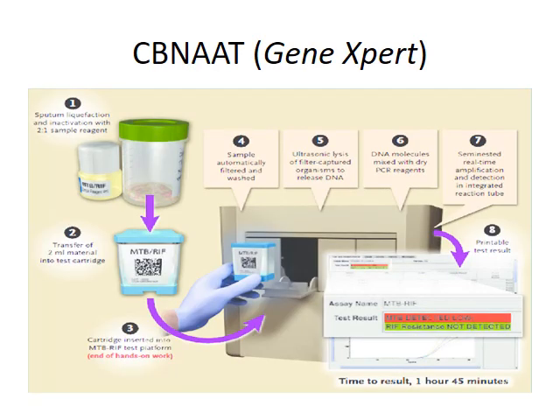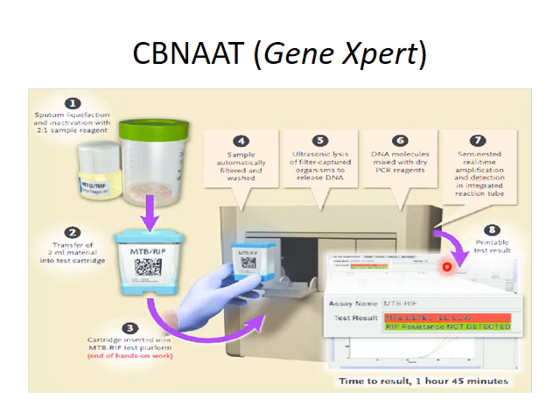The entire GeneXpert procedure: first the sample is prepared, then transferred to the cartridge, and the cartridge is inserted into the test platform. Inside the cartridge, the sample is automatically filtered and washed. DNA is released with the help of ultrasonic lysis. These DNA molecules then mix with dry PCR reagents, and finally, with the help of real-time amplification, detection is done in the integrated reaction tube. The output is seen in the software connected with GeneXpert.